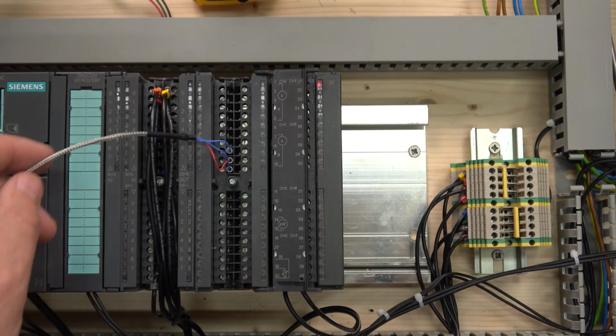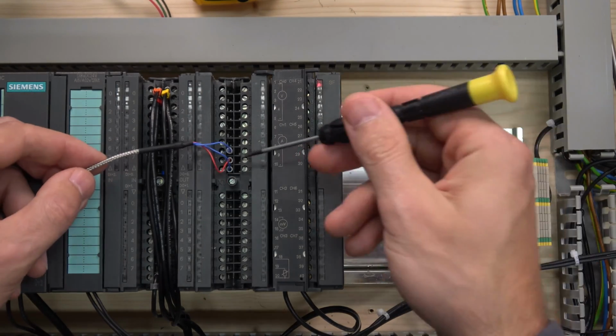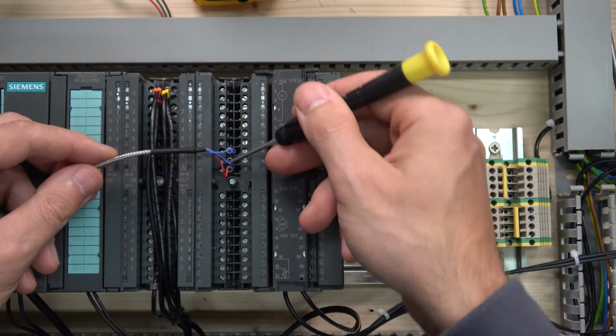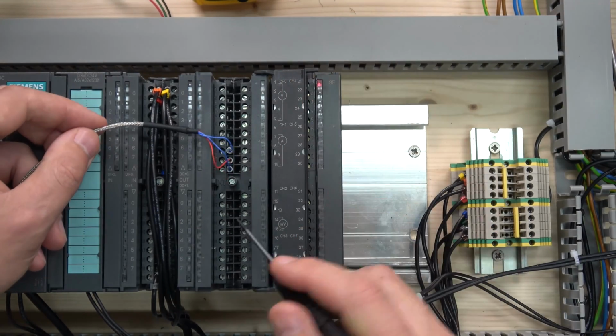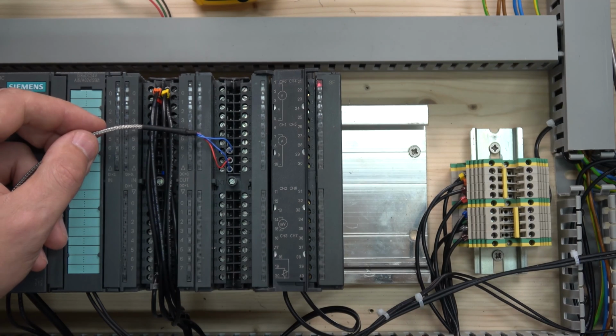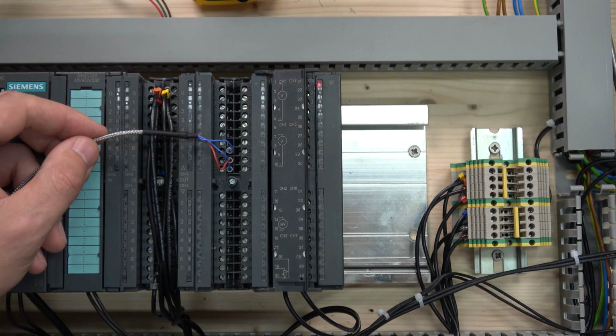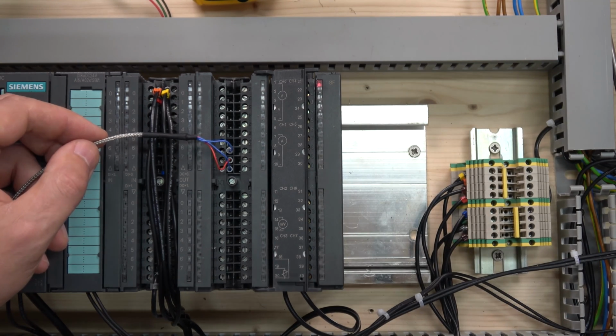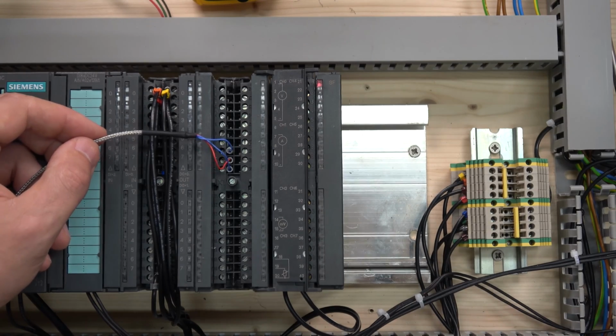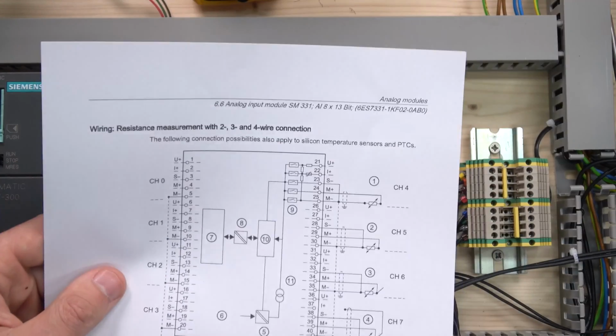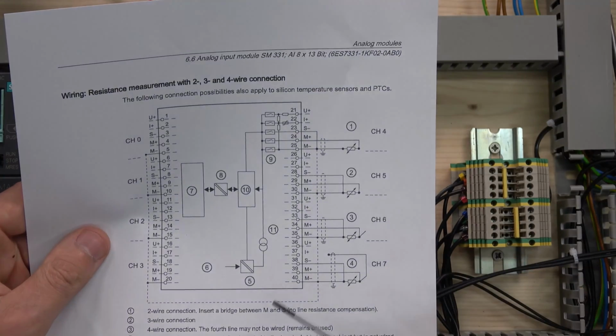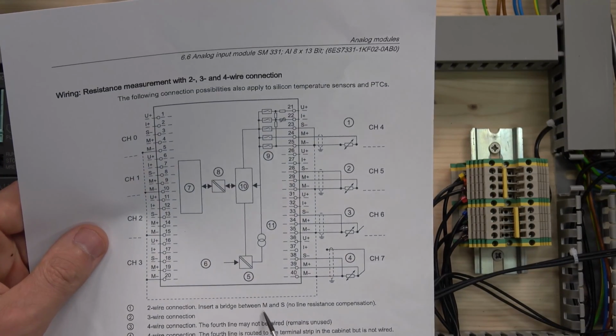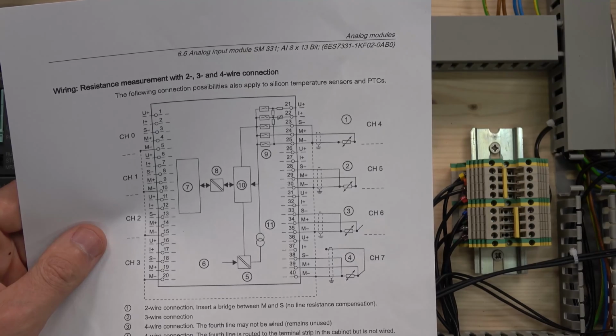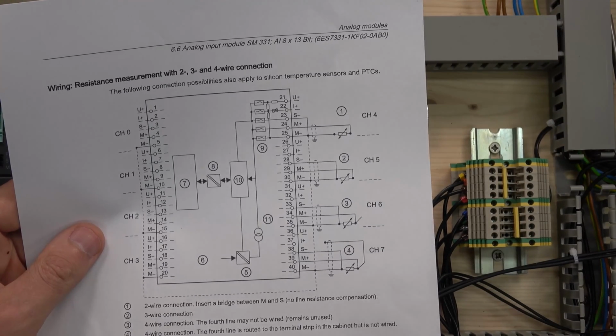I'm not sure if you watched the last video. If not, for this probe you will have the red cable coming in here. You will have red and 2 blues. Often that is the case: red and 2 blues. I've seen temperature probes in different colors, but the most common is red and 2 blues for the 3-wire. If it's a 2-wire, you just follow exactly what the wiring diagram tells you: with 2-wire, insert the bridge between M and S. That's quite straightforward, nothing too crazy, fairly easy.